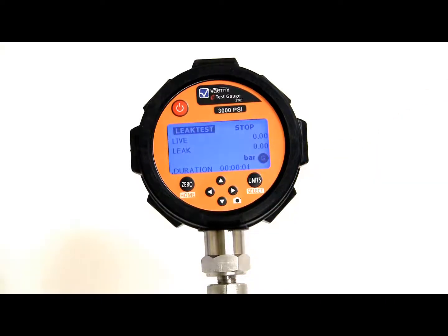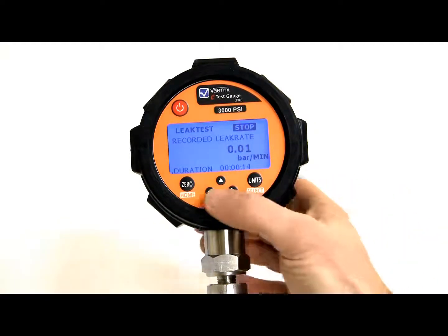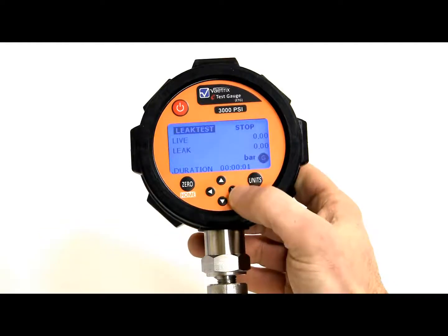So now I'm in live leak test mode. So leak test lets me check cylinders, tanks, anything that you want to check for a leak. You have to run it for 10 seconds, and it will tell you the leak rate. So I can scroll over, hit stop. It's going to tell me the leak rate in whatever units I'm in per minute. To do another test, I basically go right back, hit select, and you're starting again.